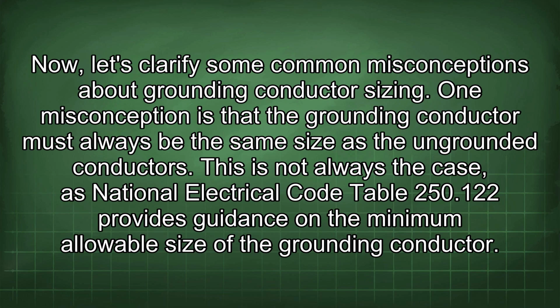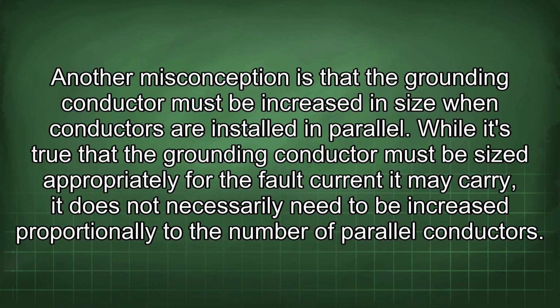Now let's clarify some common misconceptions about grounding conductor sizing. One misconception is that the grounding conductor must always be the same size as the ungrounded conductors. This is not always the case, as National Electrical Code Table 250.122 provides guidance on the minimum allowable size of the grounding conductor. Another misconception is that the grounding conductor must be increased in size when conductors are installed in parallel. While it's true that the grounding conductor must be sized appropriately for the fault current it may carry, it does not necessarily need to be increased proportionally to the number of parallel conductors.